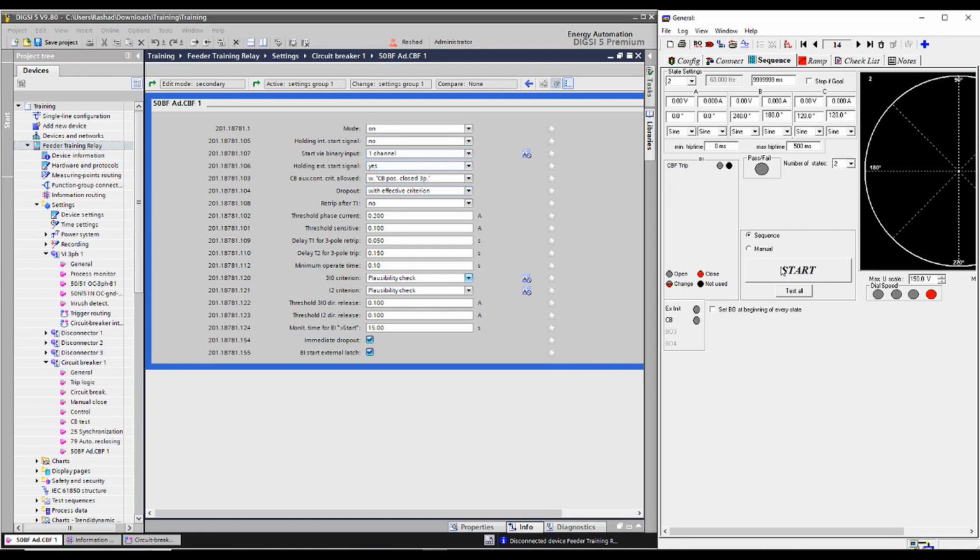Let's say you inject a binary input initiation along with the breaker condition, the current, and the data started. Now, if you remove the binary input for the breaker condition, the function won't detect. The effective criteria for you is the current.